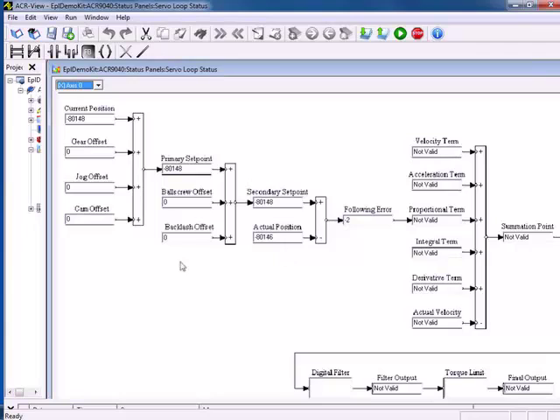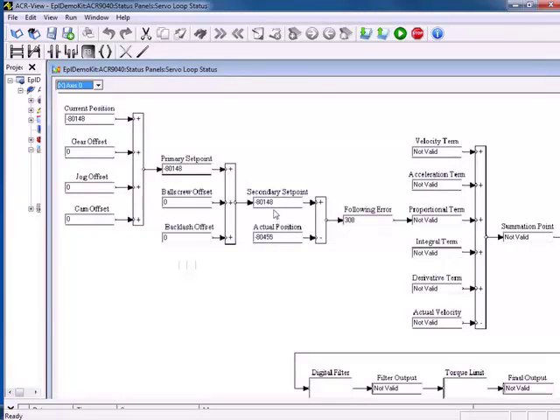If I take a hold of one of these drives here, say my X axis, you can see that my following error is increasing. I can tell you from holding onto the motor that it is increasing the current it's putting out, trying to bring it back into position. Once I've let go of it, I now have a following error of minus one to minus two counts again.